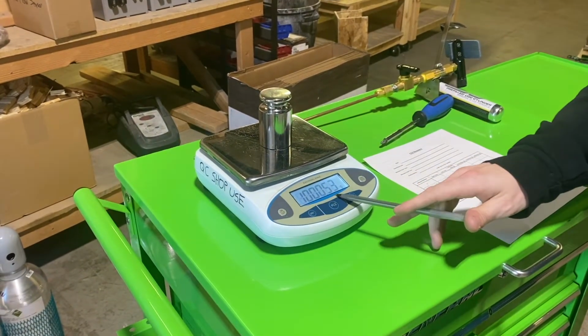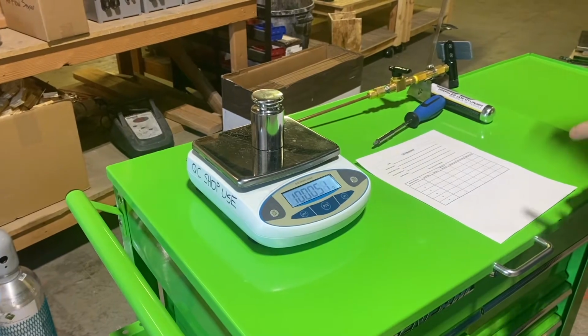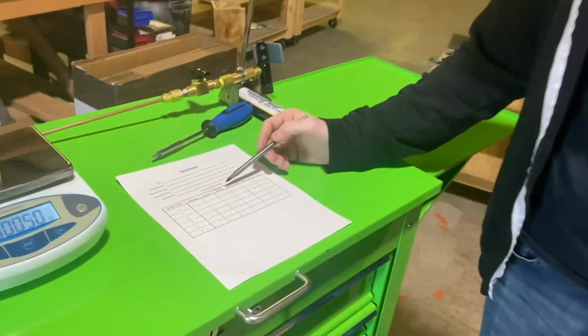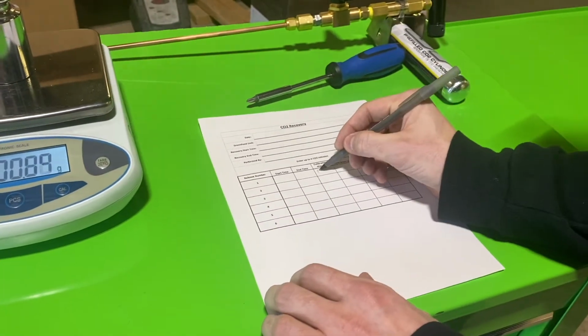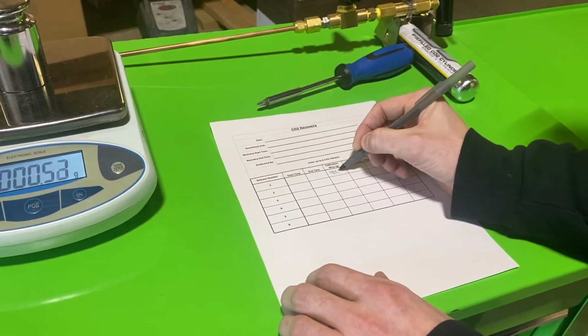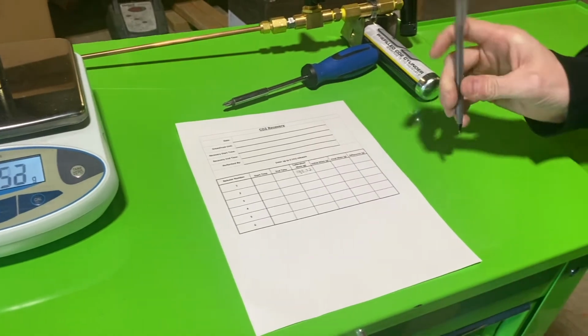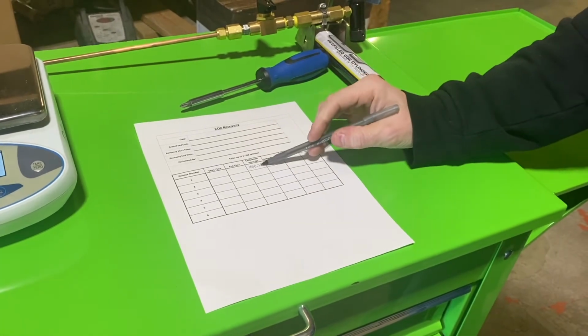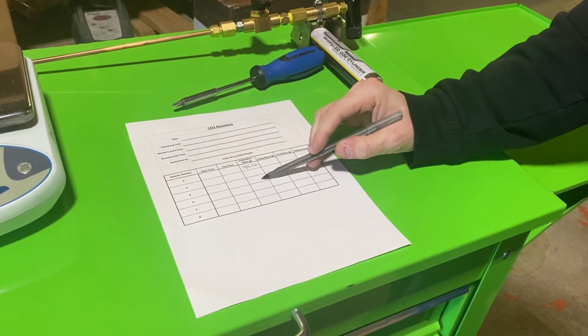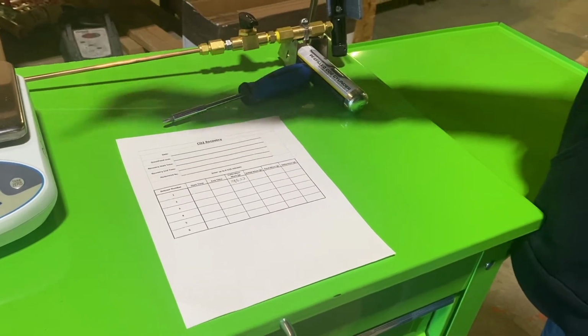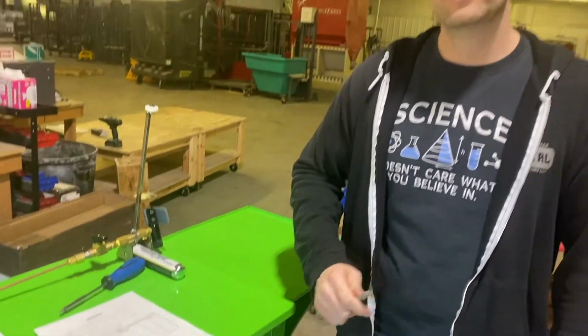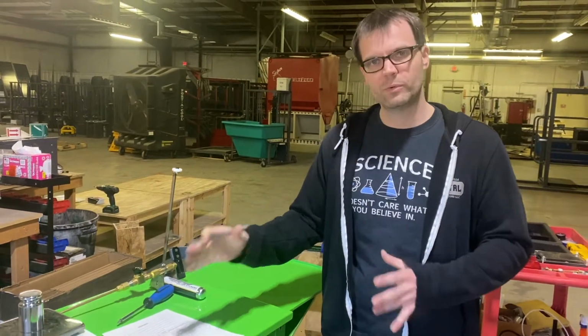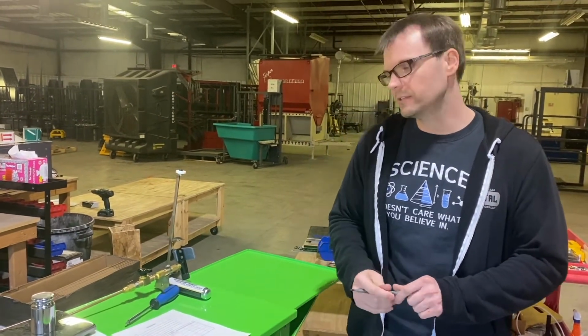So we're going to tare our scale and weigh our calibration mass. And now on our sheet of paper, we're reading that it's 1,000.52 grams. So on our recovery sheet, we're going to write down what our calibration mass was, 0.52. And every time we weigh our release device, we want to make sure that we weigh our calibration mass before that, and that'll make sure that if our scale is not reading correctly, we'll be able to catch that very easily.